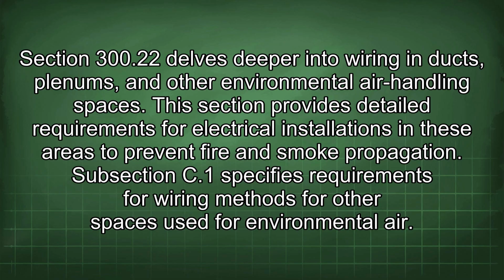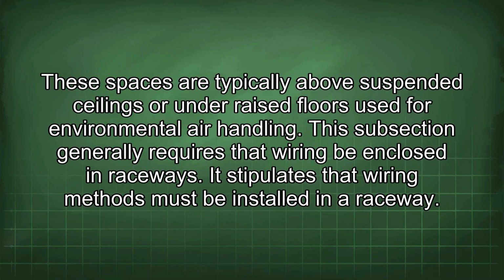Section 300.22 delves deeper into wiring in ducts, plenums, and other environmental air handling spaces. This section provides detailed requirements for electrical installations in these areas to prevent fire and smoke propagation. Subsection C1 specifies requirements for wiring methods for other spaces used for environmental air. These spaces are typically above suspended ceilings or under raised floors used for environmental air handling. This subsection generally requires that wiring be enclosed in raceways.